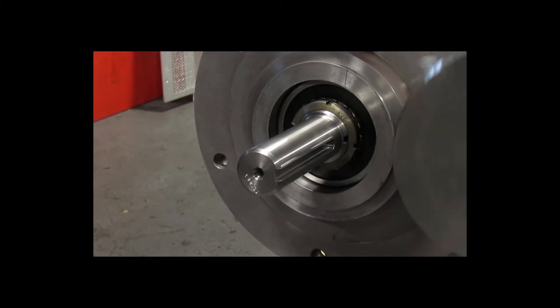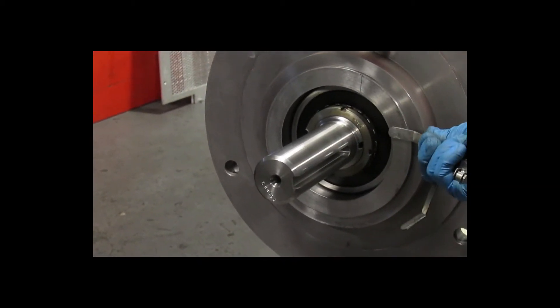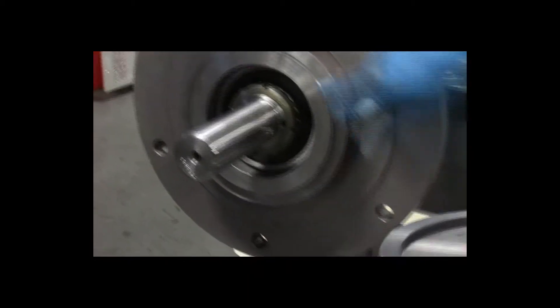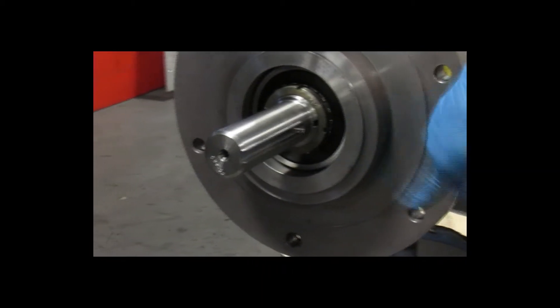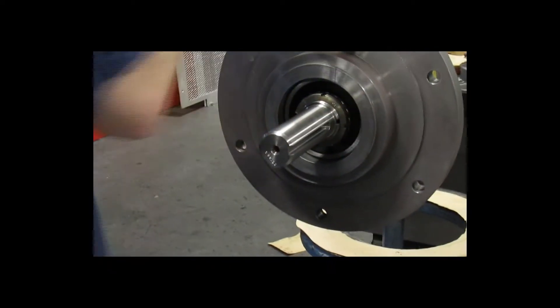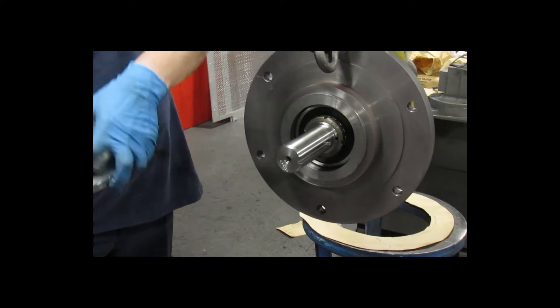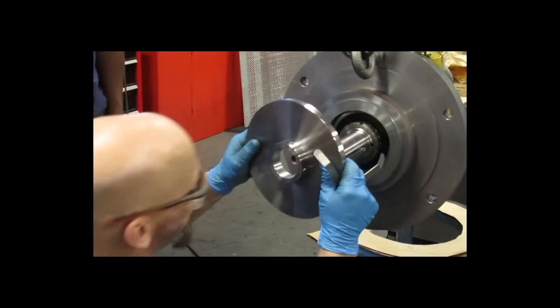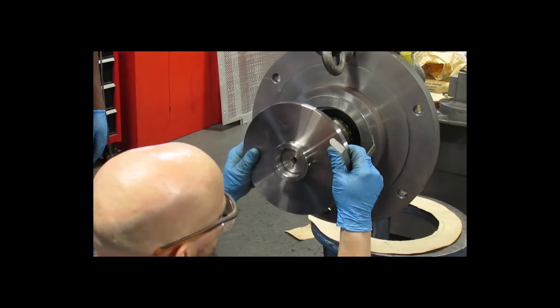The bottom flinger is set in such a manner that there is 30 thousandths clearance between it and the bottom of the bearing housing. The lower flinger must also be installed on the shaft smoothly. If it gets cocked, it's very difficult to install it fully or to remove. So it's important to make sure that it goes on straight.